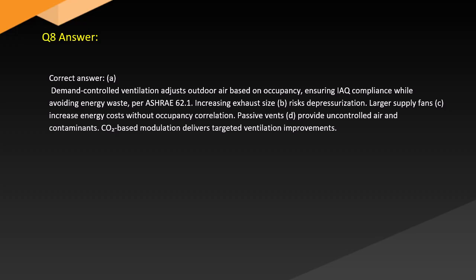Answer. Correct answer: A. Demand-controlled ventilation adjusts outdoor air based on occupancy, ensuring IAQ compliance while avoiding energy waste per ASHRAE 62.1. Increasing exhaust size (B) risks depressurization. Larger supply fans (C) increase energy costs without occupancy correlation. Passive vents (D) provide uncontrolled air and contaminants. CO2-based modulation delivers targeted ventilation improvements.